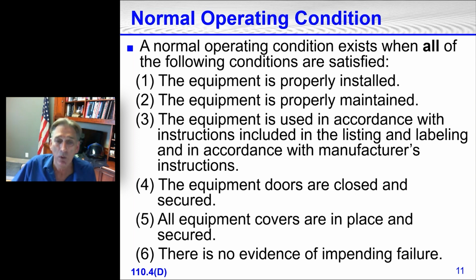Number 4, the equipment doors are closed and secured. All equipment covers are in place and secured. And number 4, the doors have to be closed and secured. I teach a lot of live seminars out there, and I've had questions come up here and there when this first came out, and someone would say, well, if the panel cover is closed to the breaker box, the panel board, I can't turn the breaker on anyway.